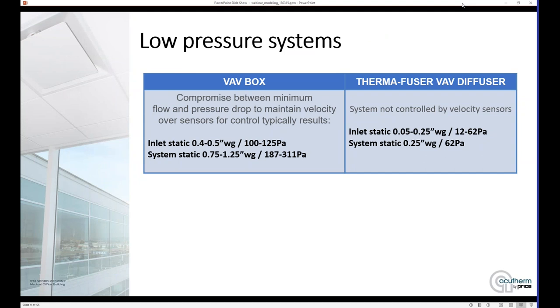When you design a traditional VAV box system, you're always making a compromise between the minimum flow of the VAV box versus the pressure drop over the box. A modern VAV box uses differential pressure sensors to calculate or measure flow, and then uses that flow as part of its control algorithm. So there's always got to be a minimum velocity, and that works out into this compromise. What it typically means from a pressure point of view is you usually end up with an inlet static on the box of anywhere from 0.4 to 0.5 of an inch. Working that back to your fan, you're looking at system statics of anywhere from three-quarters to one-and-a-quarter-inch water gauge.